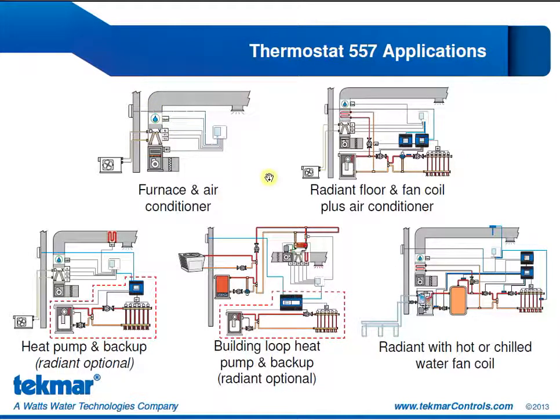Our second traditional equipment application features a radiant floor and fan coil plus an air conditioner. We have a first stage of heat from the radiant floor, a second stage of heat with the fan coil, and up to 2 stages of cooling with the air conditioner. We again have the humidifier in the ductwork for humidity control.